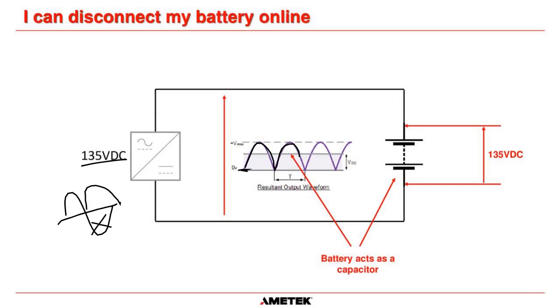This is a 0 volt line. This is probably around about 140 volts, the max. And we're going from 0 to the max, and then it's called pulsating DC. Okay, it's still DC because it's all above the 0 volt line, but it's not what you would expect out of a modern day DC system. You would expect a nice flat DC. So therefore, when you have a battery connected to this system, the battery acts as a capacitor. And what it does is it fills in these gaps, because remember, in a battery, you have plates. Okay, and any plate that is in parallel with each other acts as a capacitor. So the battery has capacitance and acts as a filter itself.